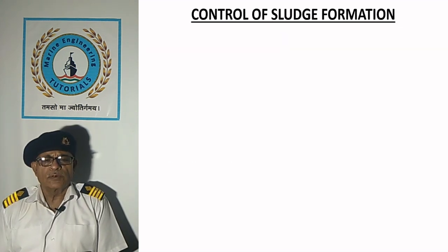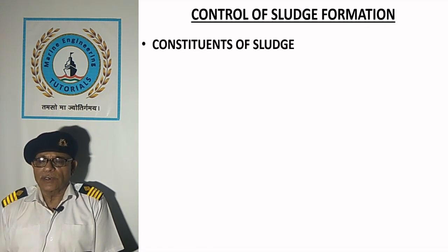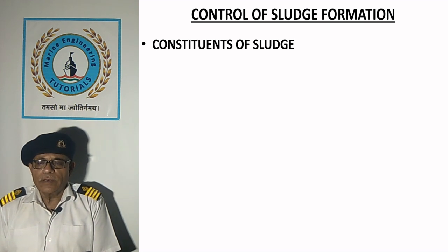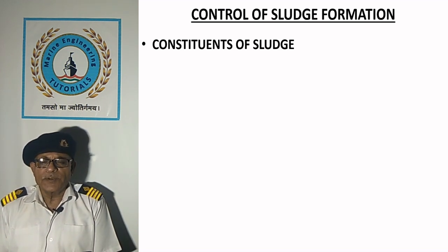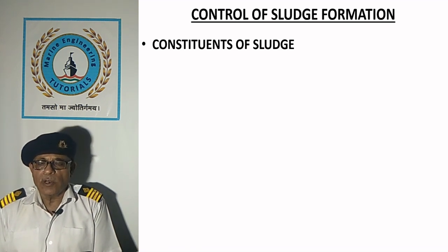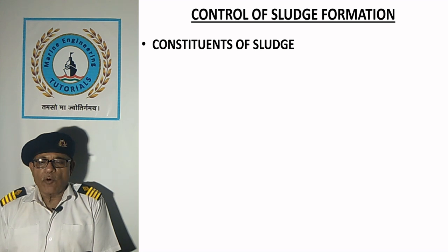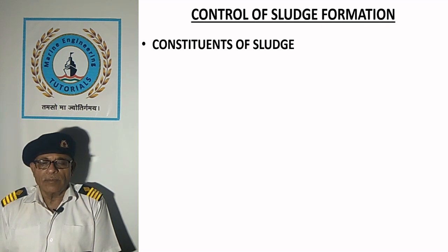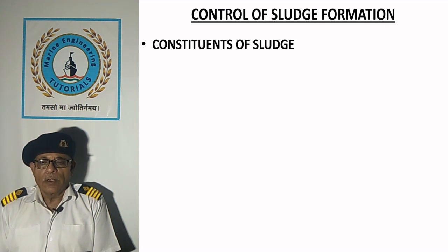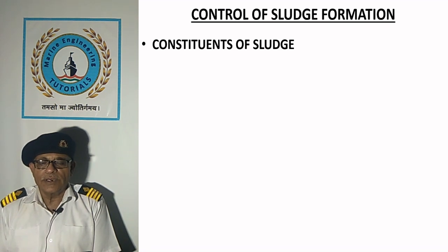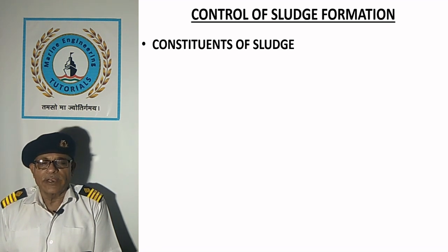Control of sludge formation. Constituents of sludge: salts suspended in water or precipitated by chemical reaction can form sludge in the boiler. Similarly, if oil gains entry into the boiler it also forms sludge on heat transfer surfaces. Deposition of sludge on heat transfer surfaces reduces heat transfer greatly, resulting in rupture of tubes due to overheating.